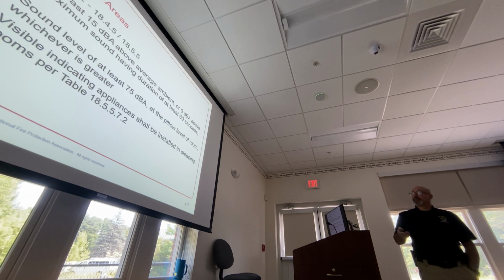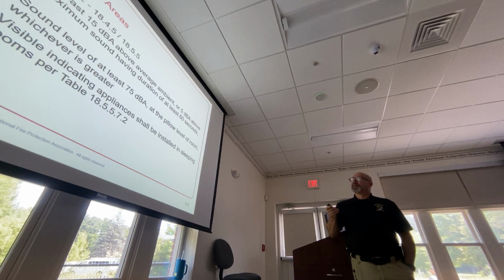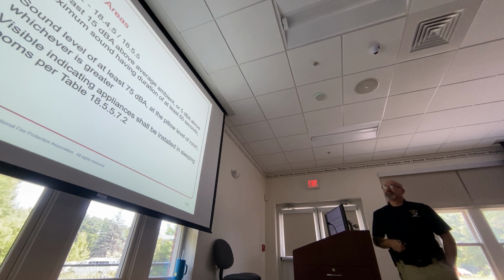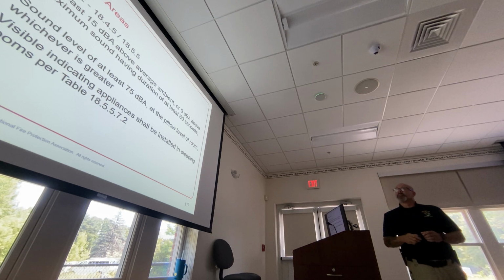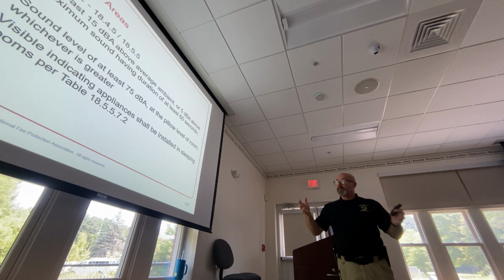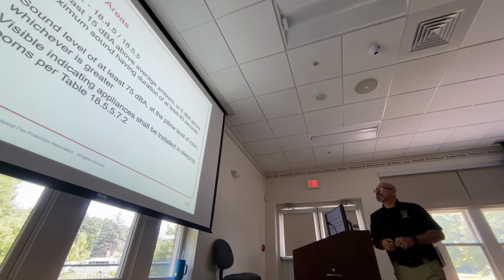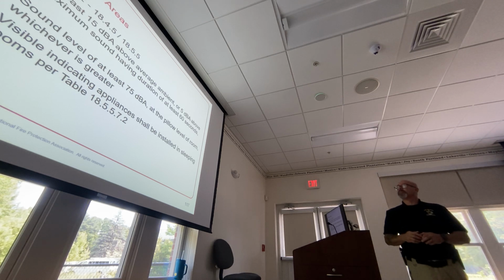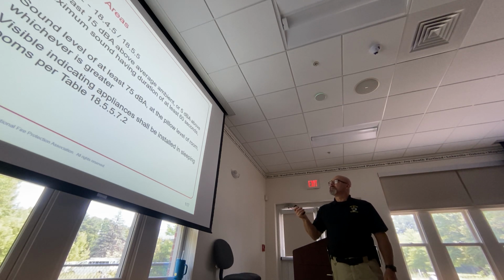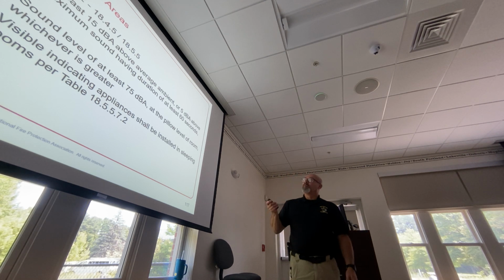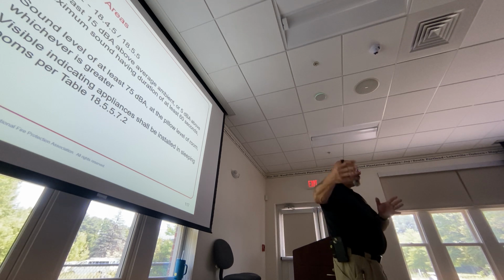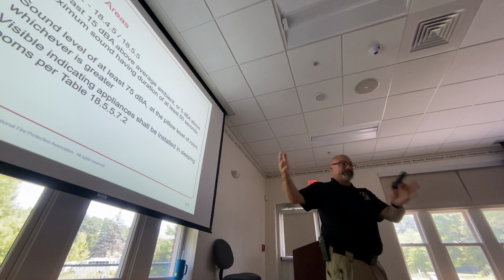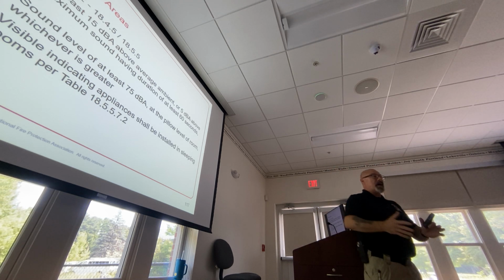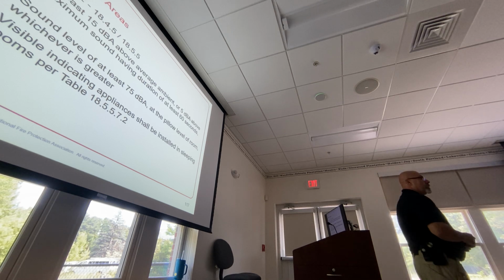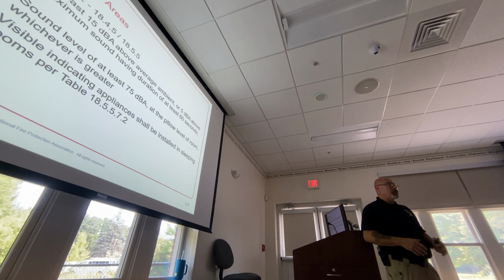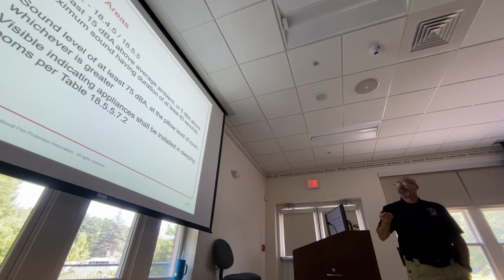Let's see. Oh yeah. 18.4.5 and 18.5.5, again, important to have. At least 15 decibels above the average ambient, again, normal sounds when it's quiet, that's the average. Or 5 above the maximum sound having a duration of at least 60 seconds. In sleeping areas, that sound above average ambient may be a ventilator machine. It may be some other type of machine, an LVAD machine, that helps somebody with their heart, keeps it pumping, whatever. If that's a constant sound that may be a little bit louder, you have to meet these requirements.